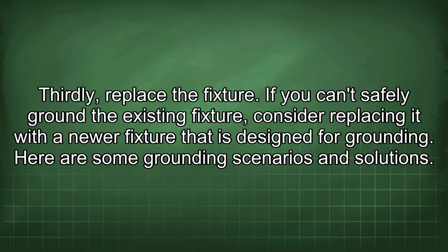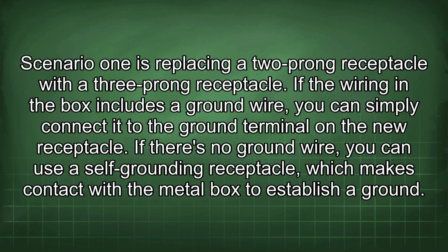Here are some grounding scenarios and solutions. Scenario 1 is replacing a two-prong receptacle with a three-prong receptacle. If the wiring in the box includes a ground wire, you can simply connect it to the ground terminal on the new receptacle. If there's no ground wire, you can use a self-grounding receptacle, which makes contact with the metal box to establish a ground.